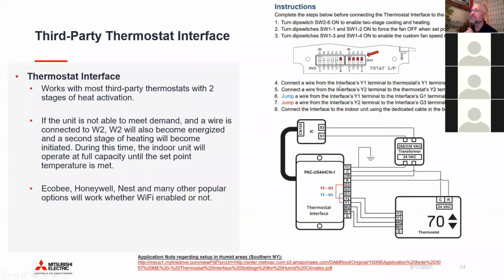There's one dip switch in particular that I really want to bring your attention to, and it's this 2-6. When the thermostat interface comes from factory, all of these dip switches are off. And in 99% of the cases, you're going to turn on this dip switch 2-6. That one basically allows the Mitsubishi system to operate using its variable speed algorithm. If it remains off as it is from factory, then anytime the thermostat interface says, I've got a call for heating, it's just going to go to full speed. And as soon as the heating call stops, it's going to shut off the system.